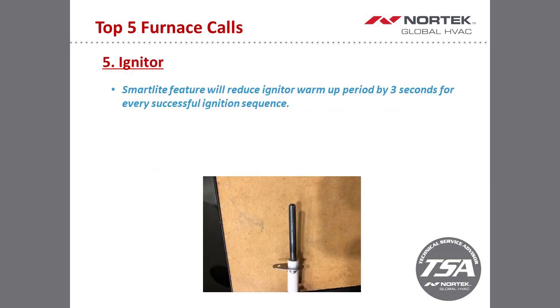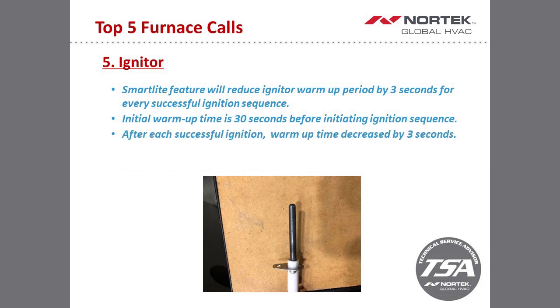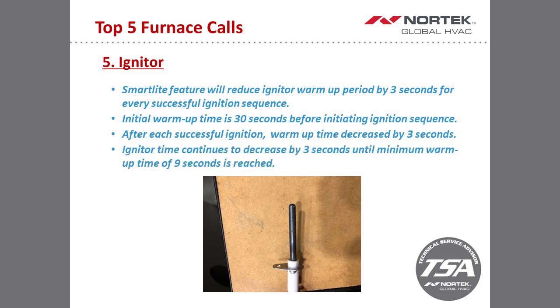Also, on this slide, we have the Smartlite feature. For the guys that are not familiar with Smartlite, basically it reduces the igniter warm-up time by 3 seconds on every successful ignition. So the initial startup sequence is going to be a 30-second warm-up time, and then with every successful ignition, it will decrease by 3 seconds, all the way down to a 9-second warm-up time. That is a feature that we have on our furnaces.